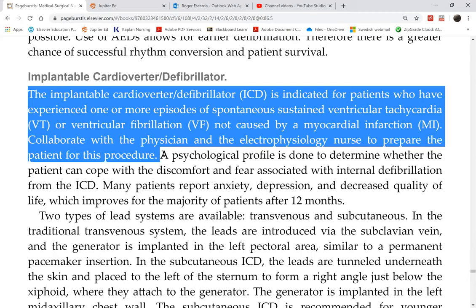Okay, so this is an implantable defibrillator. Because it's small, does it deliver really strong electrical shocks? No, it's just the same. So if this is going off, of course, you don't want to touch the patient. Sometimes they malfunction and fire.